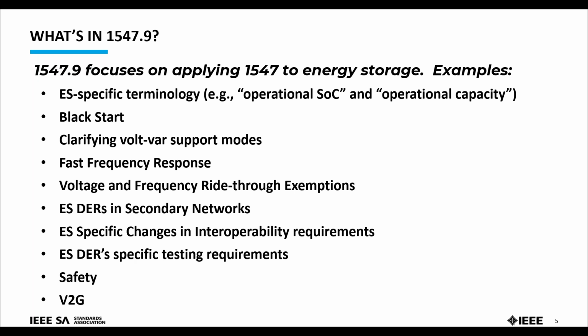It also clarifies volt-var support modes. In the base standard it was always intended that energy storage be included, but some parts were written in a fairly solar-centric way. One example: the reactive power support modes were only defined for positive output power—in other words, for energy storage, a discharge mode. There was no definition of volt-var support modes for charging mode, so we took that on in 1547.9.